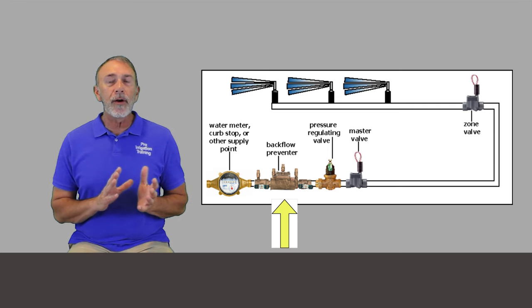But the next component, which is really the first component of an irrigation system as defined by code, is a backflow preventer. The American Water Works Association says that once the water has entered into your irrigation pipes, it cannot be sucked or pushed back into the main drinking water supply. A backflow preventer stops water from being sucked backwards or pushed backwards back into the supply point.